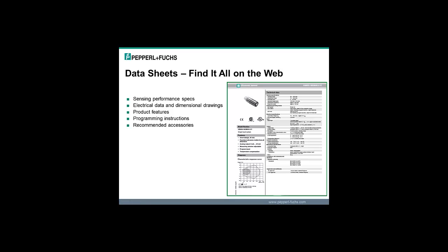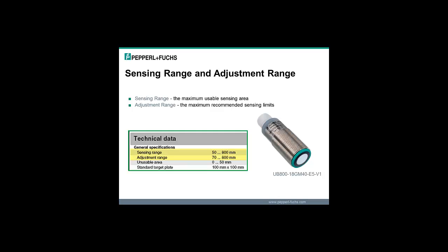Okay. Now we're going to take a look at the specifications as they relate to the data sheet, because the data sheet is the key. That's what you're going to get all your information from. That's what your customer is going to get all his information from. You can see on the right a screen capture of a data sheet that was pulled from our website, and you can find the sensor performance specifications, the electrical data and dimensional drawings, the product features, programming instructions, and also a series of recommended accessories. So everything you need to know if this ultrasonic sensor would be right for you is contained in the data sheet. When a customer is choosing an ultrasonic sensor, probably the first thing he's going to ask or want to know is, what's the sensing range?